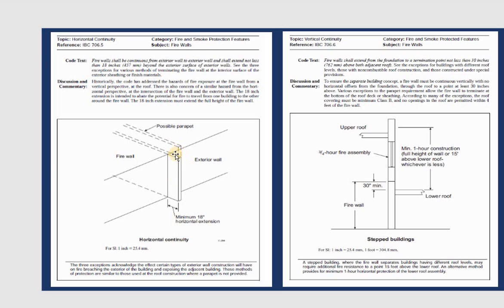The parapet on top can be three feet high, and its function is to slow fire spread from building to building and within the building. If you look at a section of a step building — meaning a building with multiple levels — you see a lower roof and an upper one. Between them, you should have minimum one-hour construction for the full height wall, or 15 feet above. That means the difference between levels is 15 feet, or you need minimum one-hour construction. If you have an opening in that area, you need minimum three-quarter hour fire assemblies.